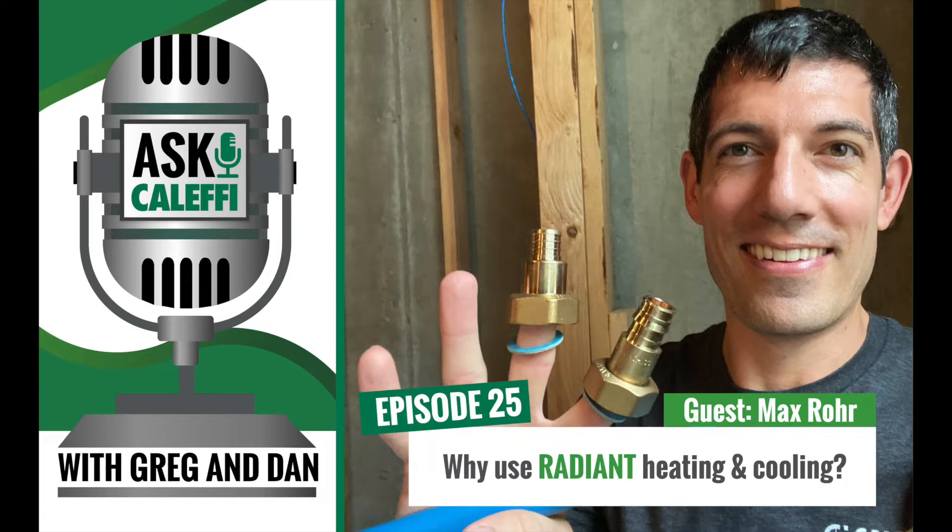I've always worked more with the PEX-A product and I like the expansion fittings. If you ever risk kinking it while laying tubing down in the floor, you're not forced to put in a coupling - you can heat it up and get it back to its original form. With Caleffi components, we actually have tailpieces with our different products for either expansion for PEX-A with an F-1960 type fitting, or for a crimp fitting that will work with A, B, or C. So we've got tailpieces that can go from any of those to our products, which is helpful. Especially at the manifold, that transition won't matter what type of PEX you have - we have a great fitting to adapt there.